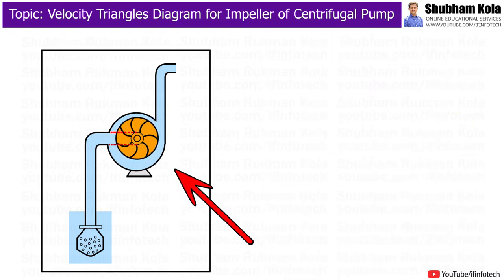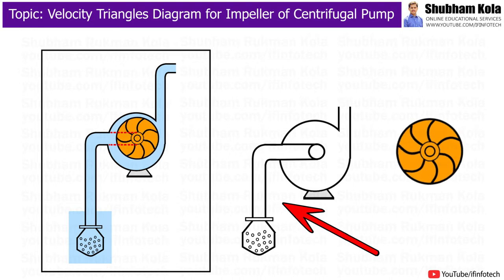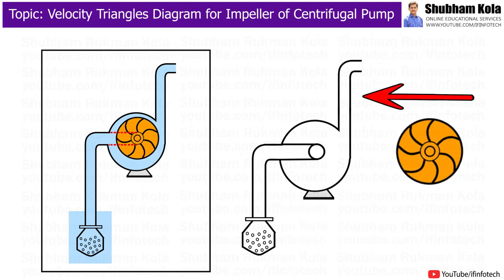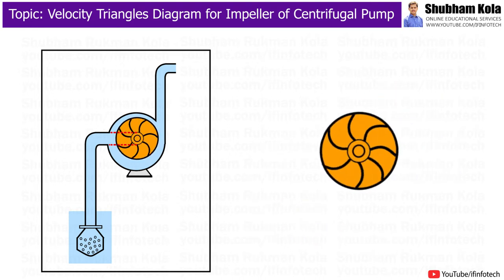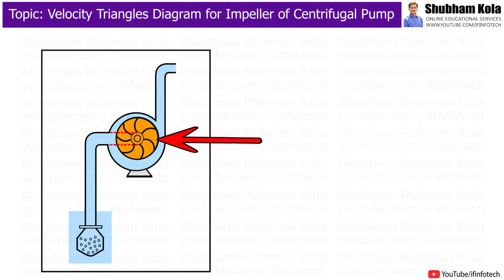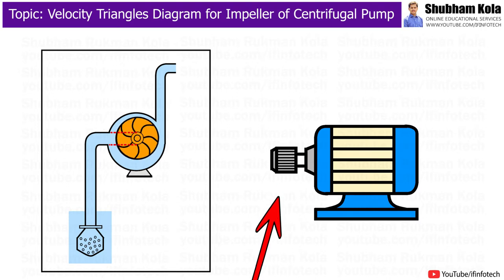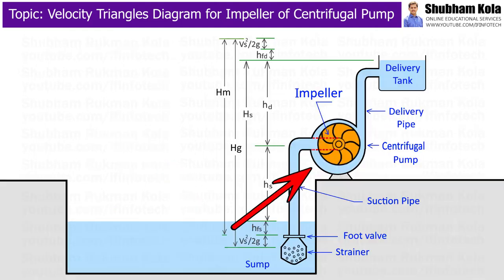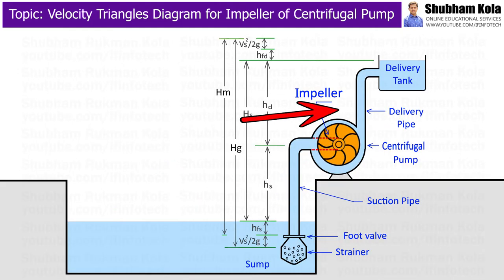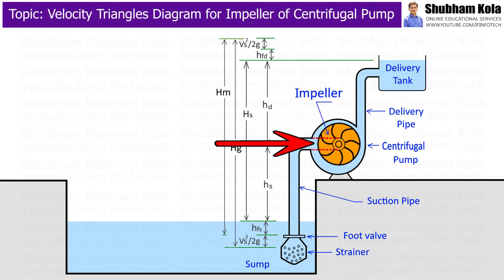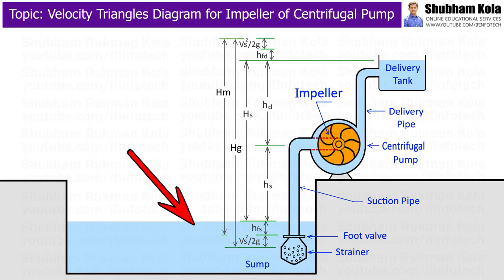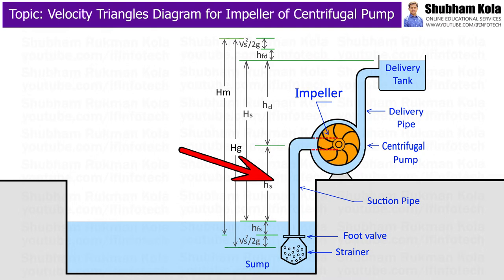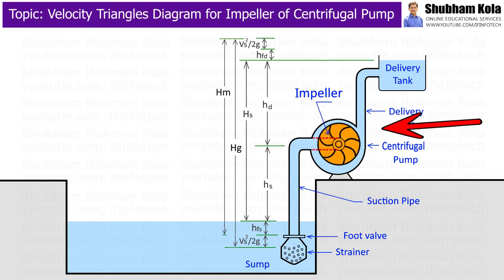The centrifugal pump consists of an impeller, casing, suction pipe with strainer and foot valve, and delivery pipe. The impeller is a rotor having a series of backward curved blades, mounted on a shaft which is usually coupled to a motor. The motor provides the required input energy to rotate the impeller. The impeller is enclosed in a volute-type casing with a delivery pipe on one side and the suction side arrangement called the eye of the impeller. The pipe connecting the sump to the eye of the impeller is called the suction pipe, and the delivery pipe connects the outlet of the pump to the point where it delivers liquid to the required height.